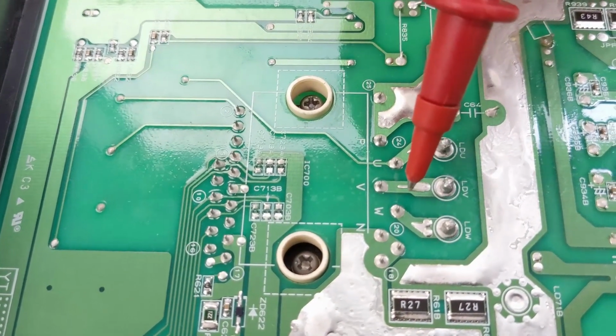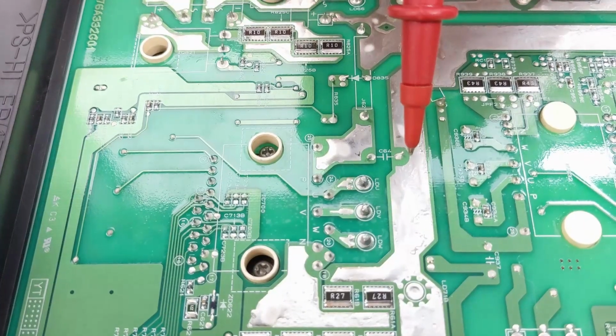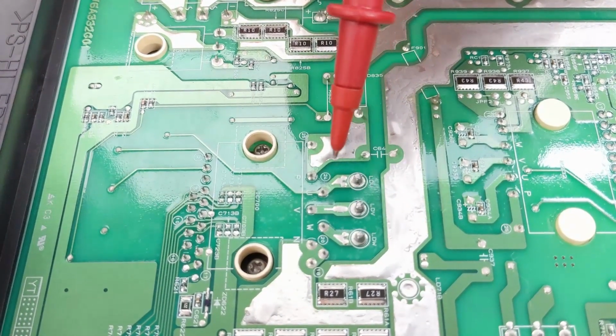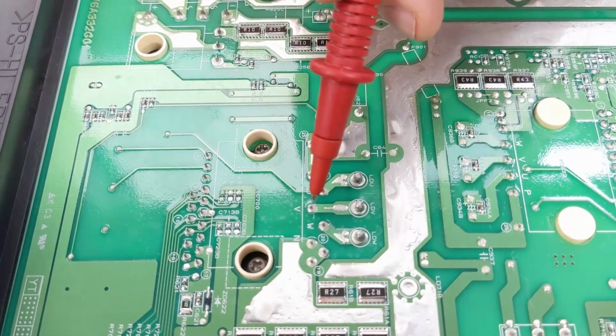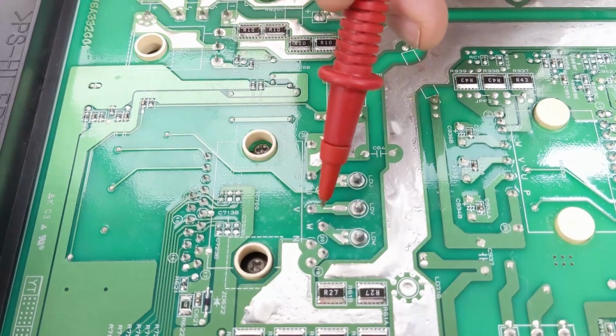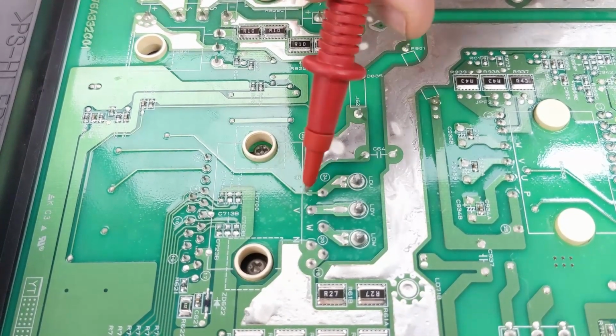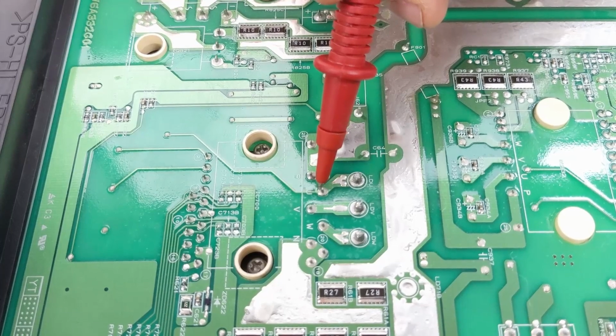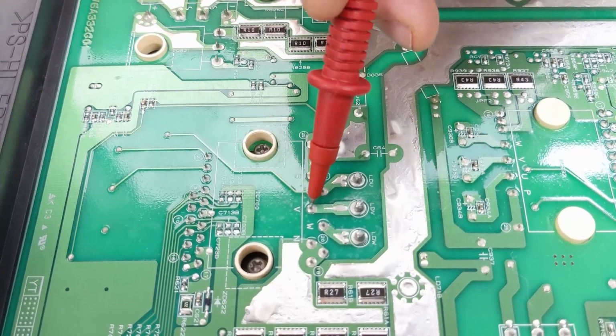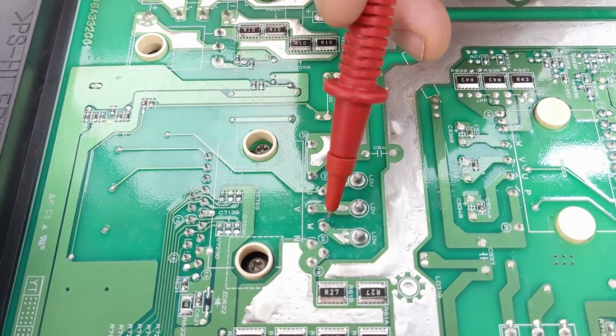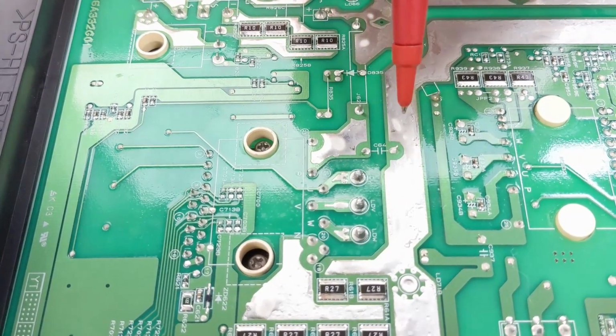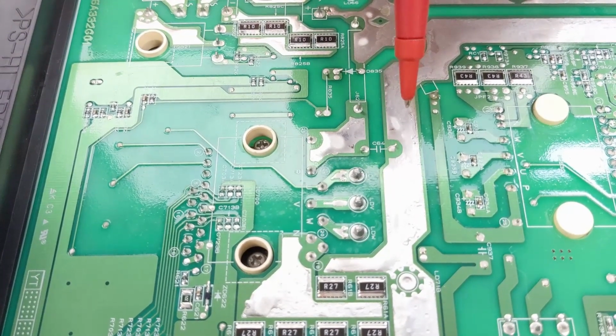So I've taken the covers off this one, so we then can go to the test points at the top here. So I can then test the outputs that we're going down to the compressor. So there's my W, V and U. I can put a multimeter between U and V and W and U to test those outputs that are supposed to be going to the compressor to do that inverter testing.